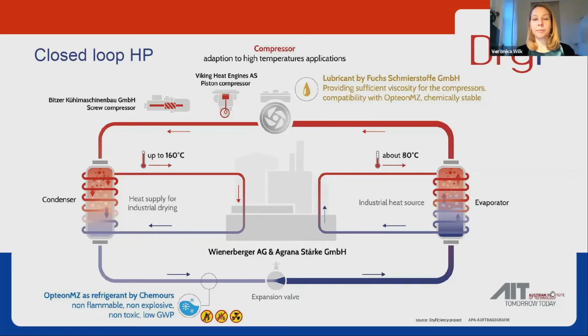The closed loop heat pump requires lubrication for the compressors, and we have a lubrication specialist within our consortium, Fuchs, also based in Germany. They developed a lubricant compatible with the refrigerant and the high temperatures. For that, it's important to ensure thermal and chemical stability so the fluids don't get too reactive with each other and start degrading too quickly.